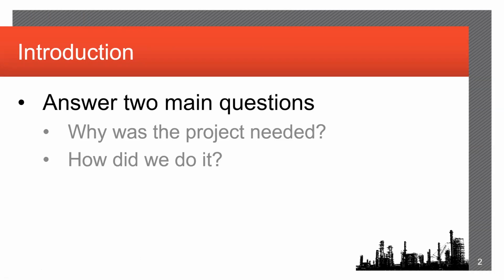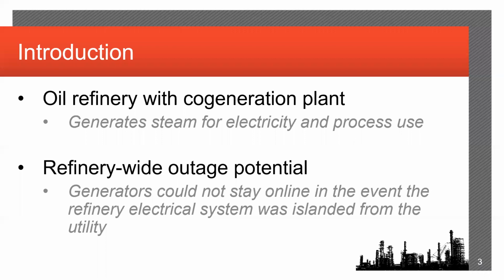So in the presentation, we're going to answer two main questions. The first one is, why was this project needed? And the second one, which is a little more complicated, is how did we do it? As I said, this is an oil refinery, and the oil refinery has a steam boiler that creates steam for two purposes. One, they use it in their refining process, and they also use some of that steam to run 3 steam turbines to supply part of their electrical needs. Whenever these generators were originally installed, they were intended to run with a connection to the local utility. And as such, anytime that they were ever disconnected from the local utility, the generators could not stay online, even if they did have enough available generation to power part of or all of the refinery load.